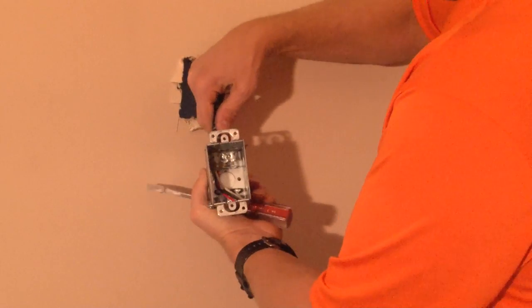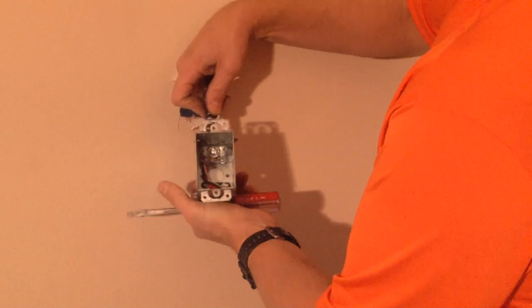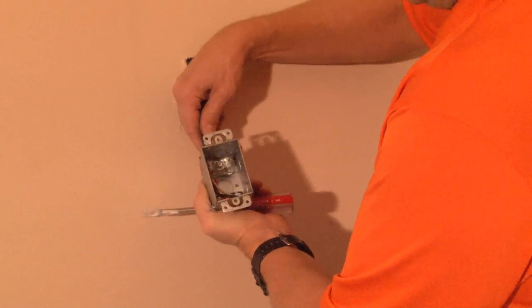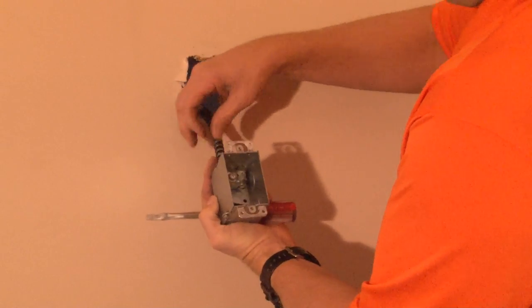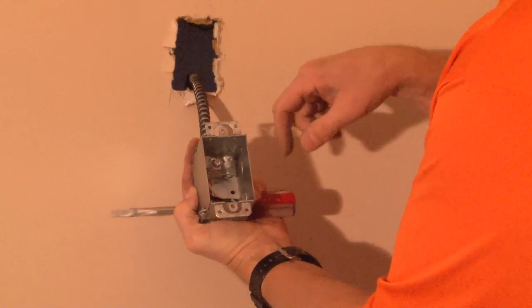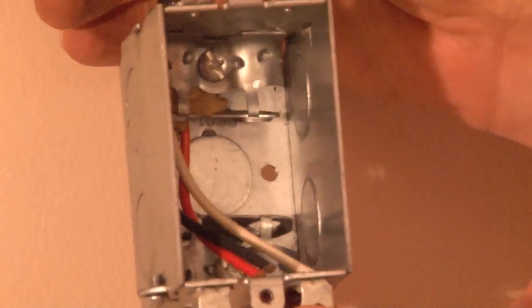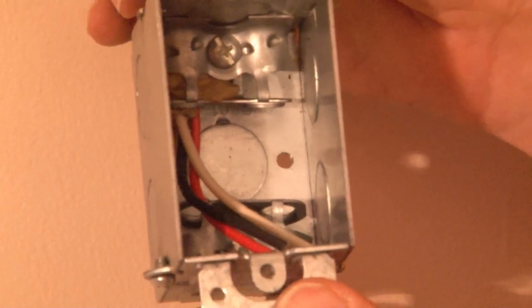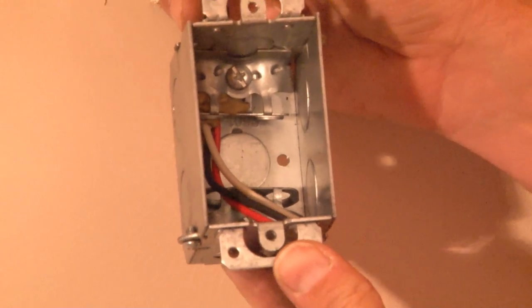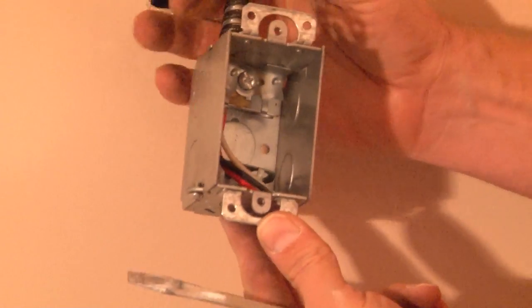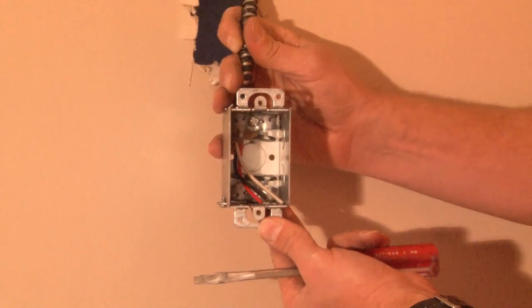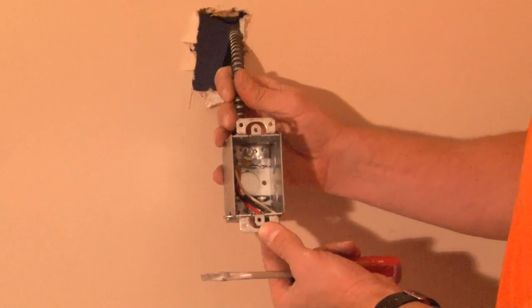You slide the flex conduit and tighten the set screw in the bottom. At this point, by tightening the set screw, it clamps on the outer sheathing of the metal and allows the electrical conductors to be free inside the box.